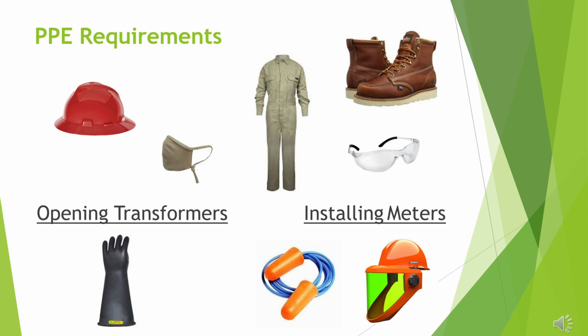So once you've opened the transformer, you confirm that there is no exposed primary present. You're able to take those class 2 gloves off and put on your class 0 gloves to make any secondary connections. Next, for installing meters, you have to have 2 additional pieces of PPE. You have to have your face shield when you're installing a meter, and you actually have to have your hearing protection. So again, the top area is required within the 10 feet at any time, and then you have your specifics for installing meters and then for opening transformers.